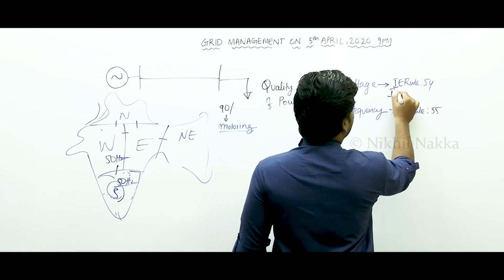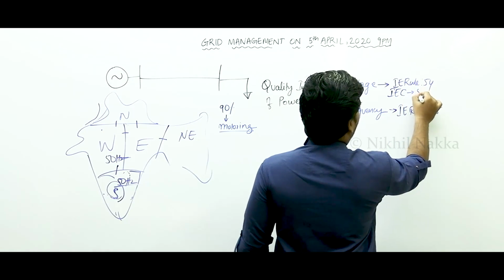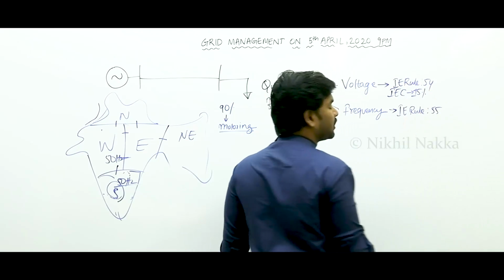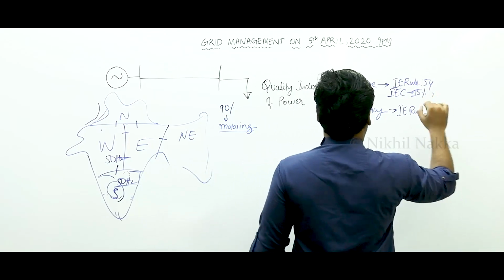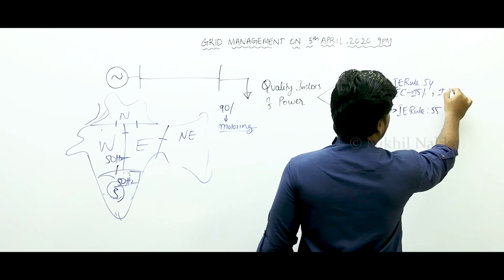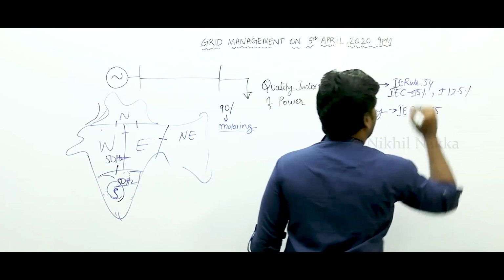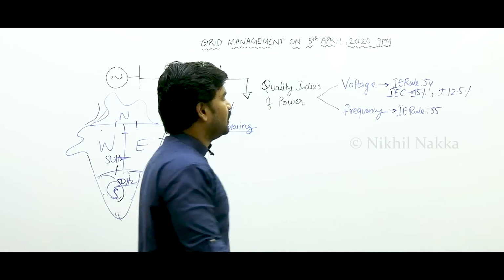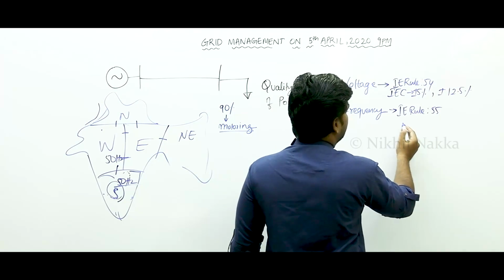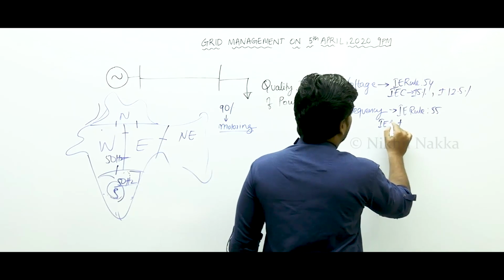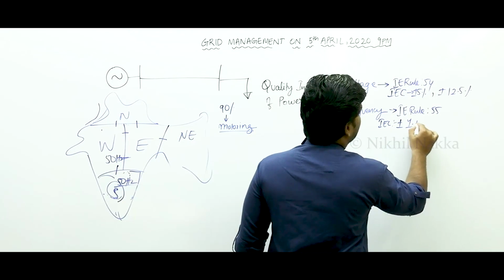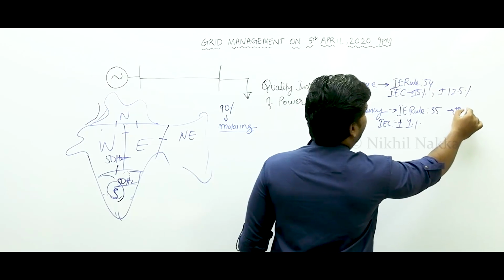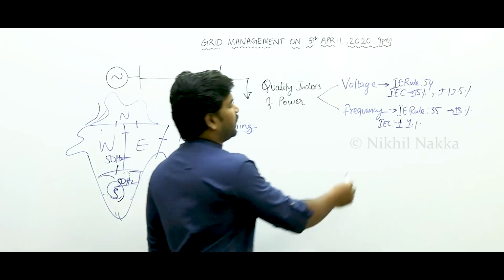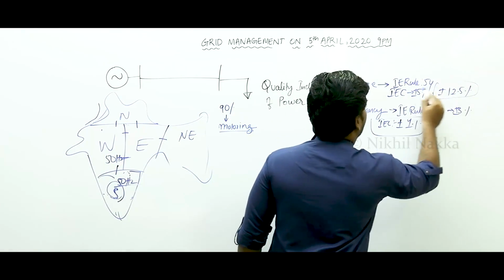So we will go with the international standard, the IEC standard. As per IEC standard, the voltage variation allowed is plus or minus 5% for medium voltage and low voltage circuits, and for EHV or HV transmission lines, plus or minus 12.5% voltage variation is allowed. As per IEC, the frequency variation allowed is plus or minus 1%. If you take the IE rule, frequency variation is plus or minus 3%, but still we will go with the IEC rule only. Of course the Electricity Act says its own value, but we will follow the IEC rule.